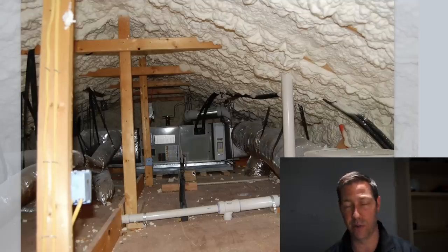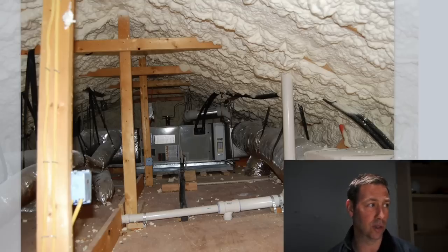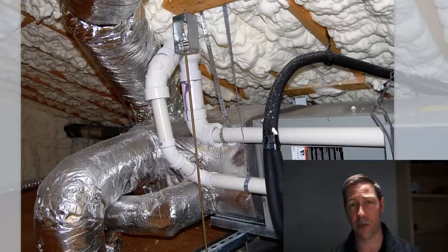Compare that with those other houses from the '70s, '90s, and today that are built with attics at 130 to 150 degrees - crazy hot. When the furnace kicks on in those unconditioned attics, it's depressurizing the house, and the house is trying to suck in air to make up for that. That's a double whammy for energy inefficiency: the ducts up in that super hot space are only around R-6 or R-8, we've got lots of radiation from the sun heating up that attic, and we've got depressurization every time the furnace kicks on from leaky ductwork.